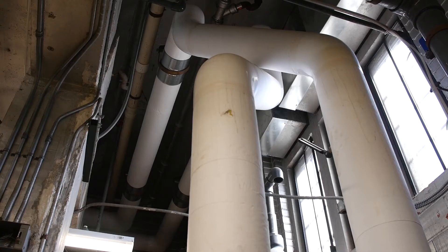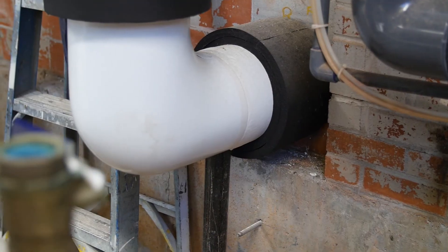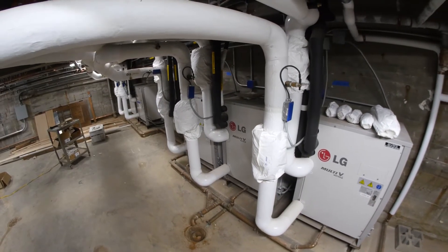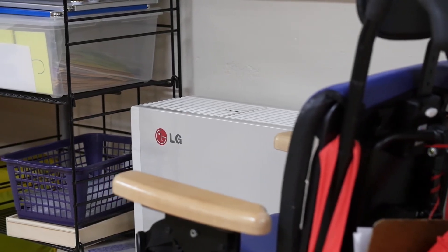The way we're exchanging and absorbing and rejecting heat is through water. We've got a central plant located in the adjacent school with a cooling tower and a boiler. It brings water over to the building and then we've got water-cooled condensing units that sit in the basement. The water-cooled condensing units are piped up to different areas and zones. We've got ducted units in some classrooms, ceiling cassette units in some areas, and a few floor console units that sit throughout the school.